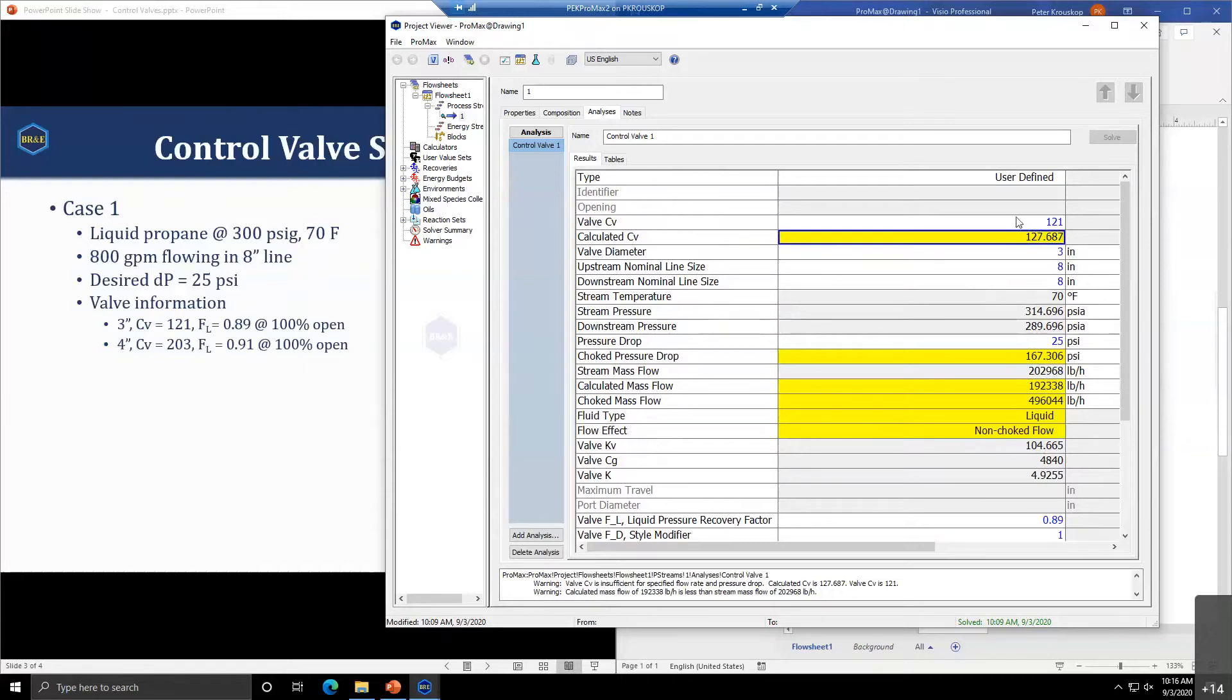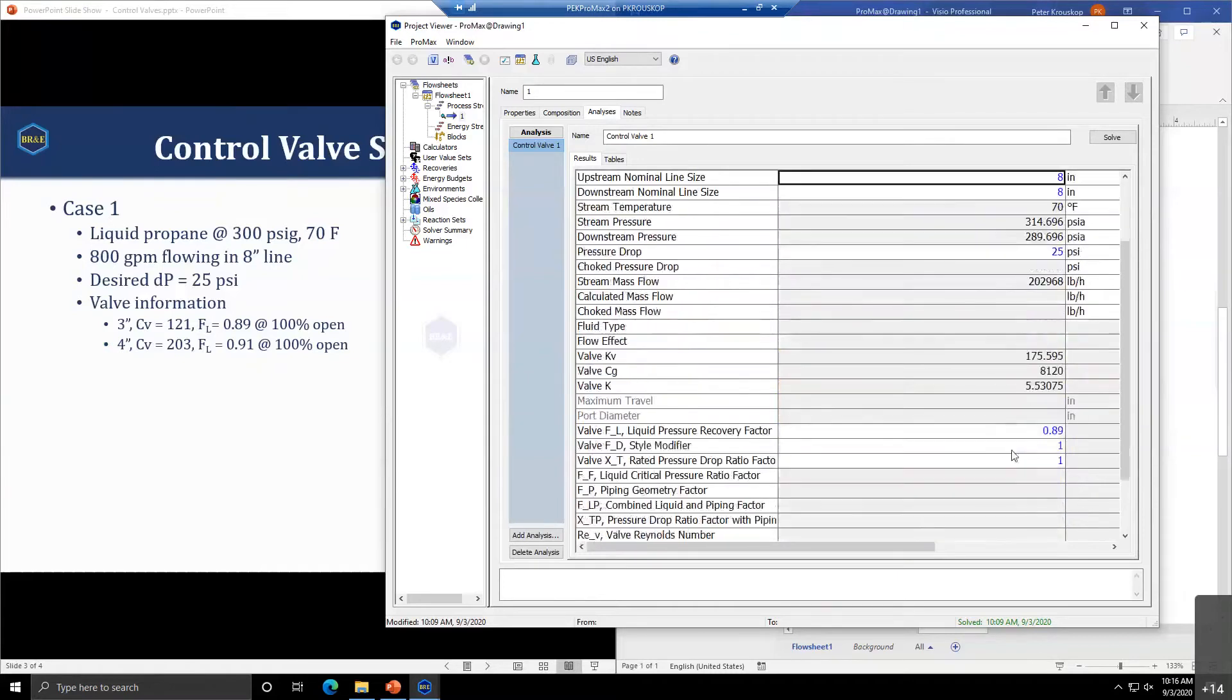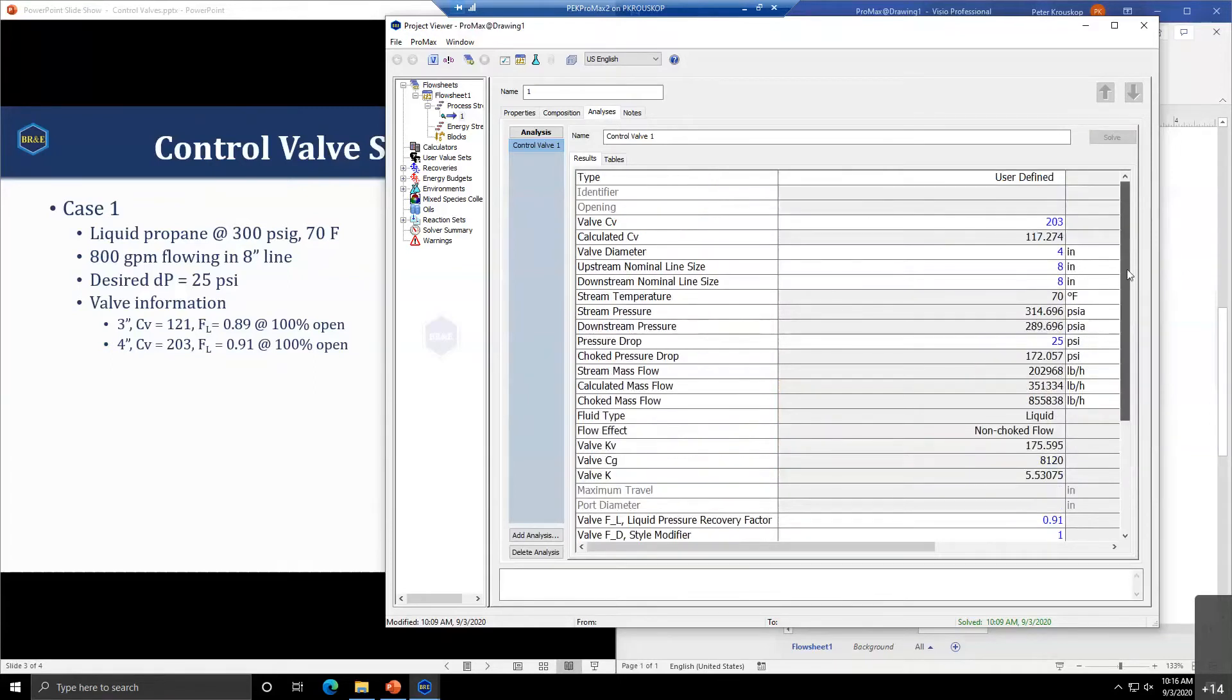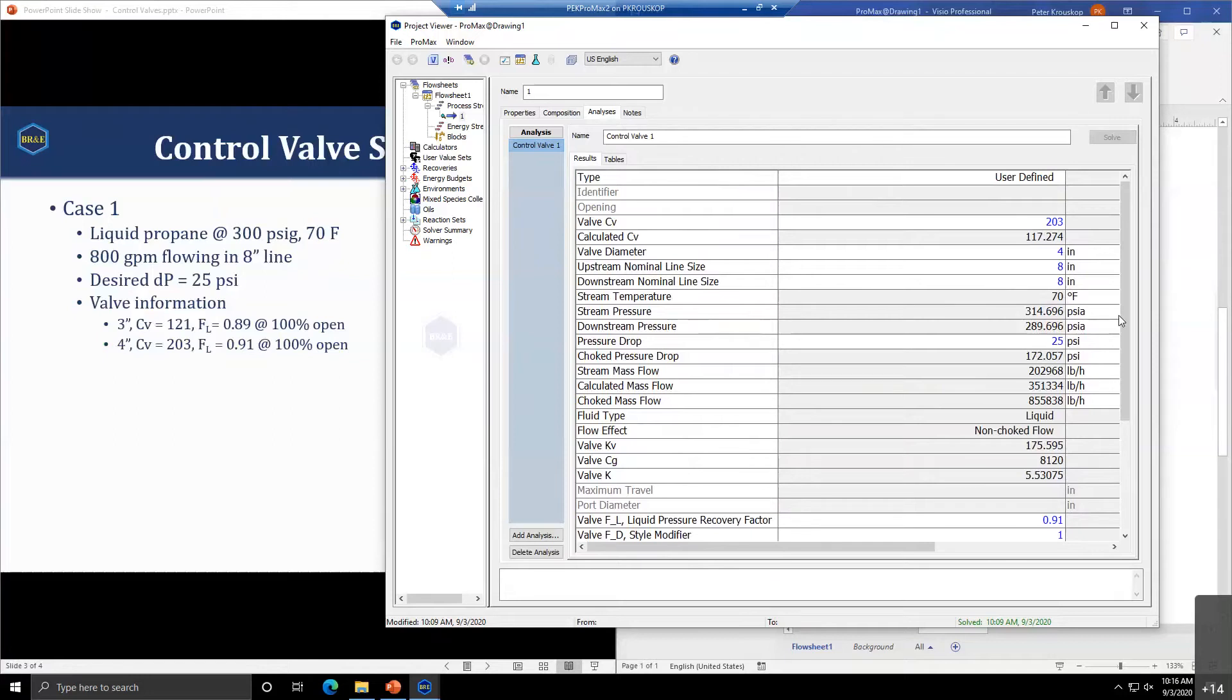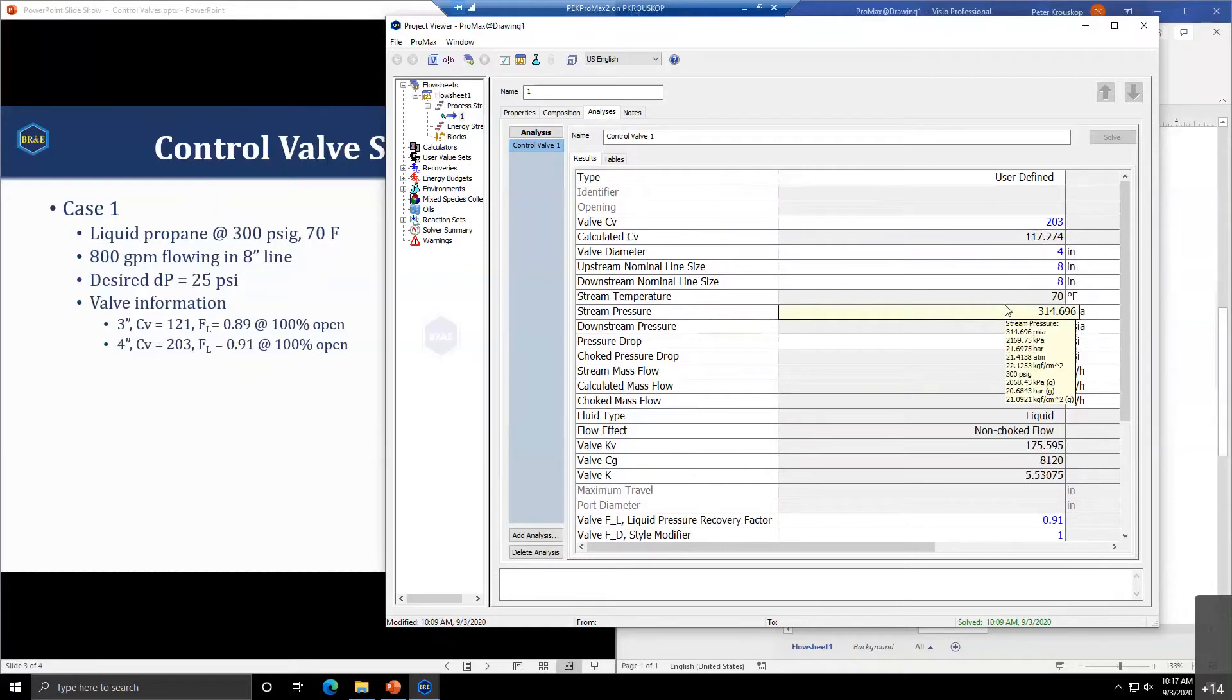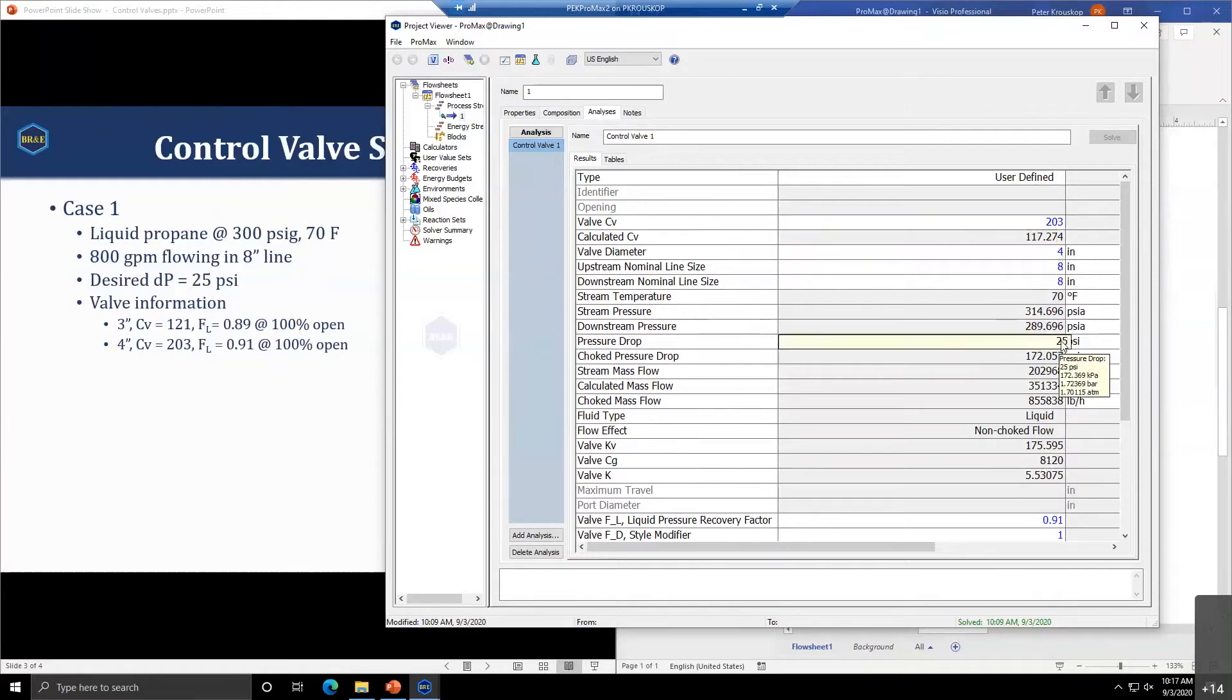If we try our larger valve, if we go to 203 CV with 0.91 FL, obviously we'd expect this one to work. When this one solves, there are no bright yellow fields. The required CV for our current flow rate is 117, so we would not be operating at full open under these conditions.